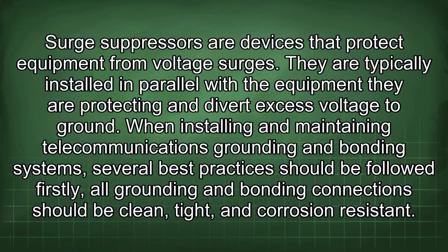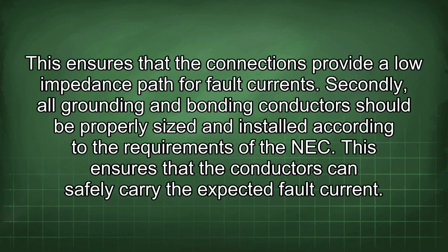When installing and maintaining telecommunications grounding and bonding systems, several best practices should be followed. Firstly, all grounding and bonding connections should be clean, tight, and corrosion resistant. This ensures that the connections provide a low impedance path for fault currents. Secondly, all grounding and bonding conductors should be properly sized and installed according to the requirements of the NEC. This ensures that the conductors can safely carry the expected fault current.